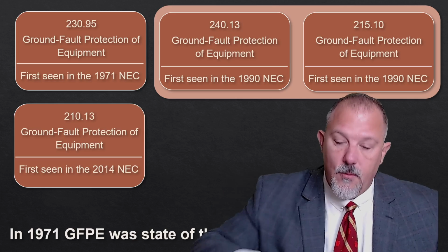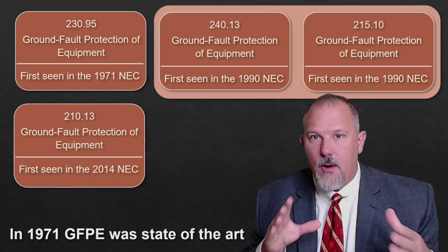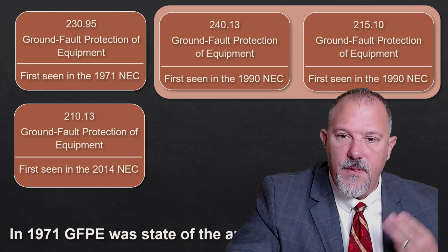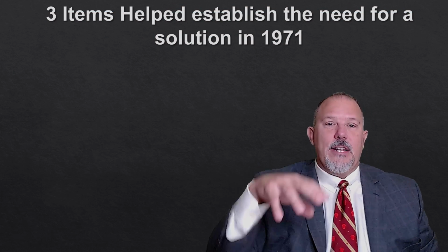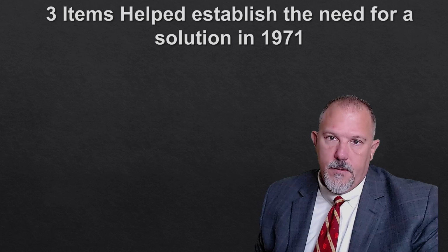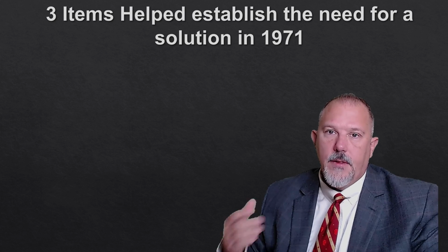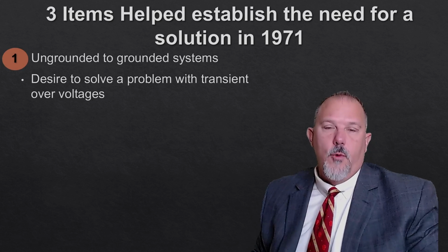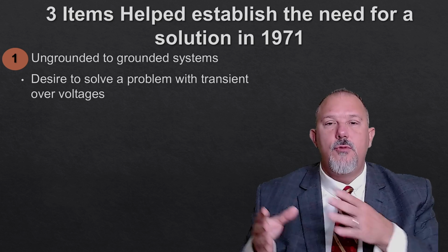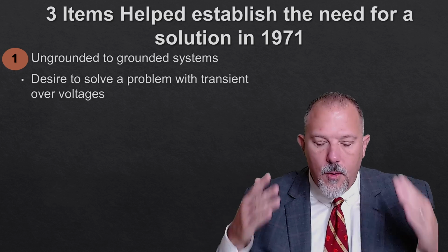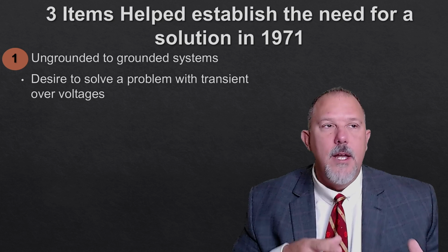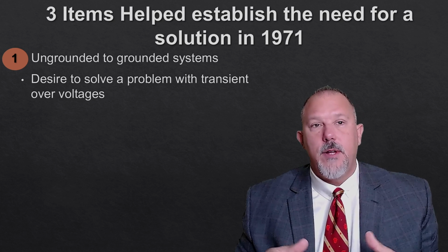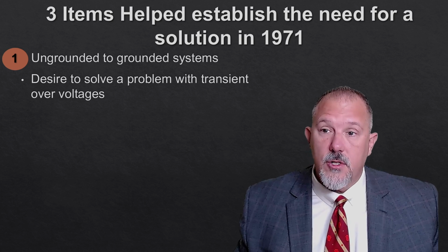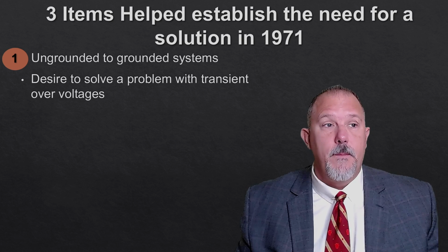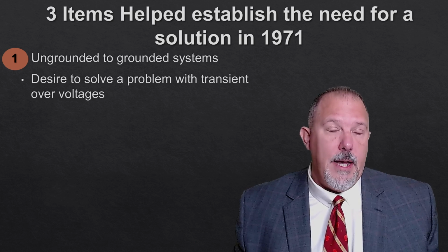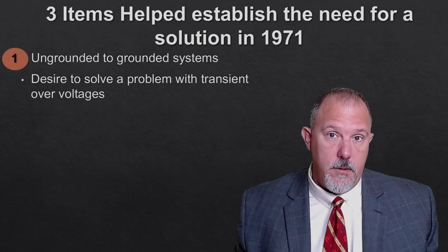So in 1971, in this era in our electrical history, there were three key things that drove the requirements in the National Electrical Code. One, we were moving from ungrounded systems to grounded systems. Why were we doing that? What were the problems with ungrounded systems? The issue that any ungrounded system experiences is transient voltages. That's the biggest problem. It's like having a boat without an anchor.